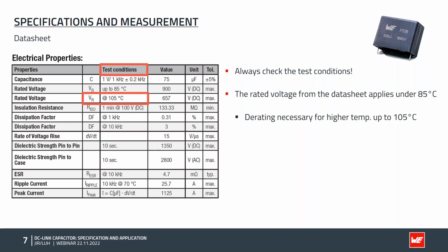Another interesting thing is that we specify this part as rated for 900 volts, but this rating is only valid up to 85 degrees Celsius. The component is also rated for 105 degrees, so there's a derating of voltage after 85 degrees. I'll go into detail later, but you have to take this into account for high temperature.